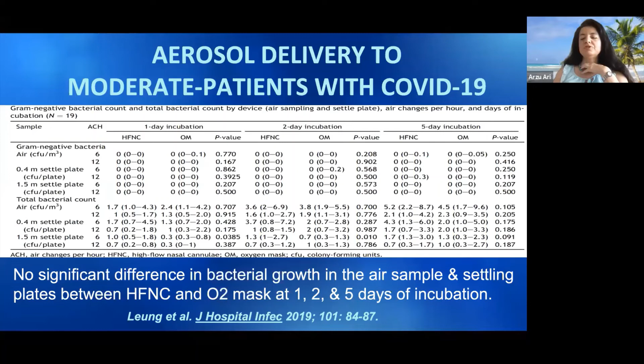So, because of all that evidence and also the publication that was released by the Chinese Medical Association, we recommend using the high flow nasal cannula in moderate patients with COVID-19. There are a couple of things that you need to pay attention to when you use the high flow nasal cannula in this patient population. First, you need to place the vibrating mesh nebulizer prior to the humidifier to improve the delivery efficiency of your device. And then, secondly, you need to make sure that the prongs are well fitted in the nares and are not loose. Also, when you use the mesh nebulizer, make sure the reservoir cap is always closed after each use.